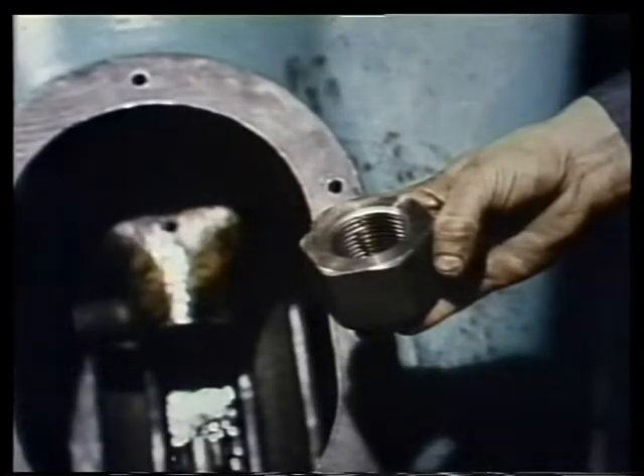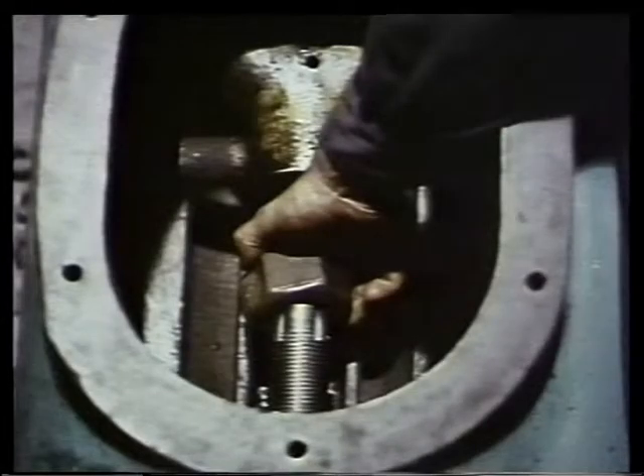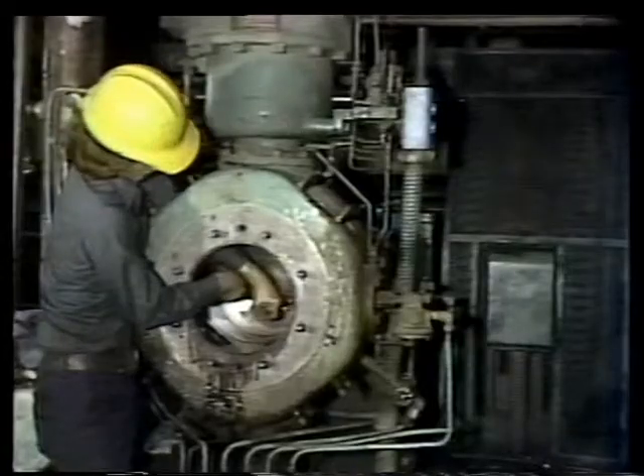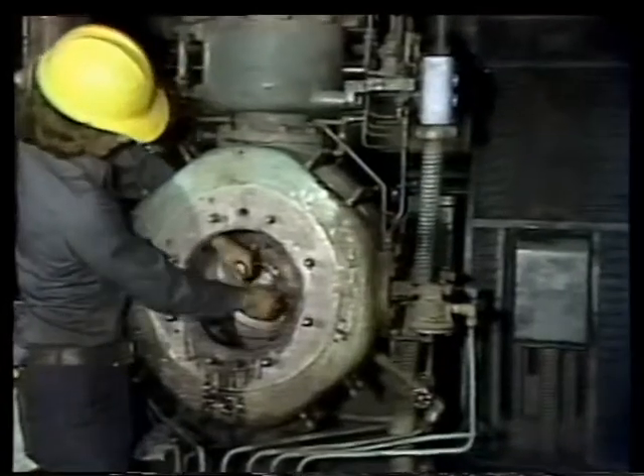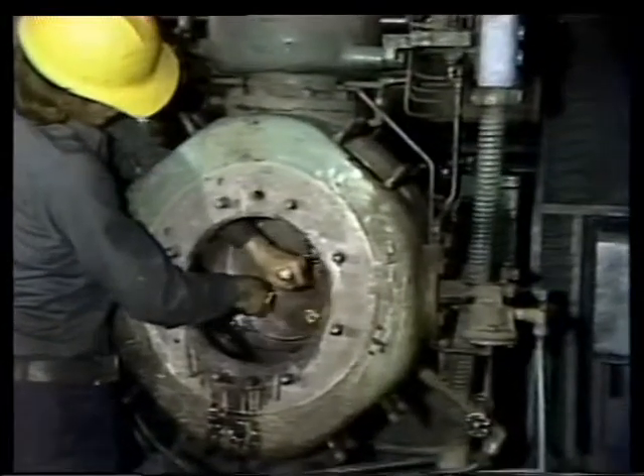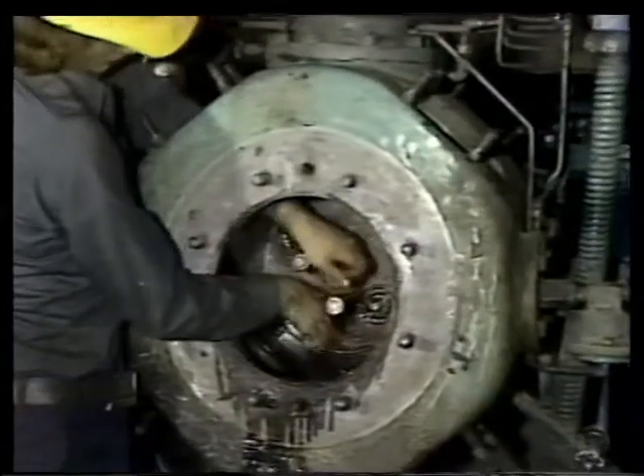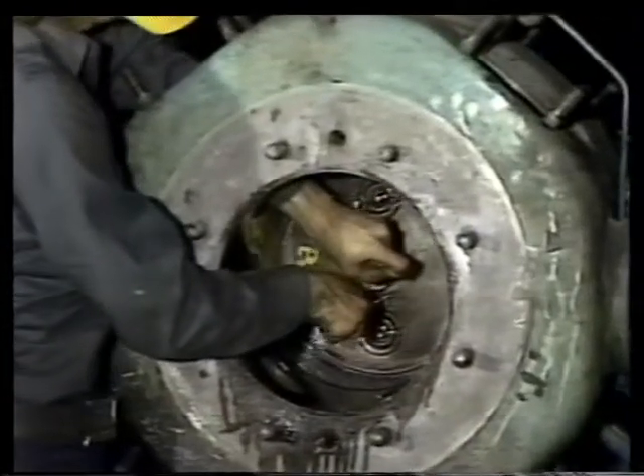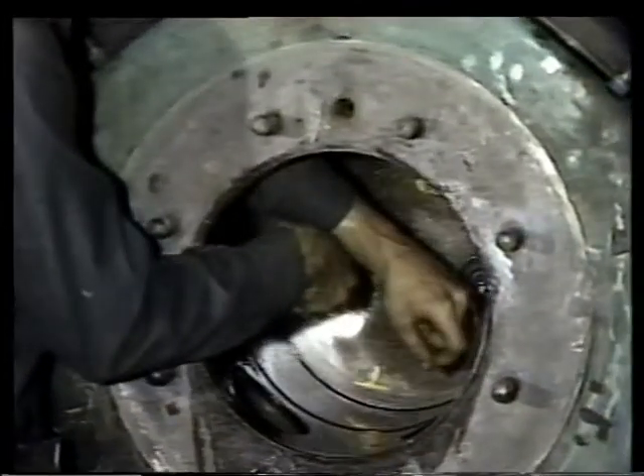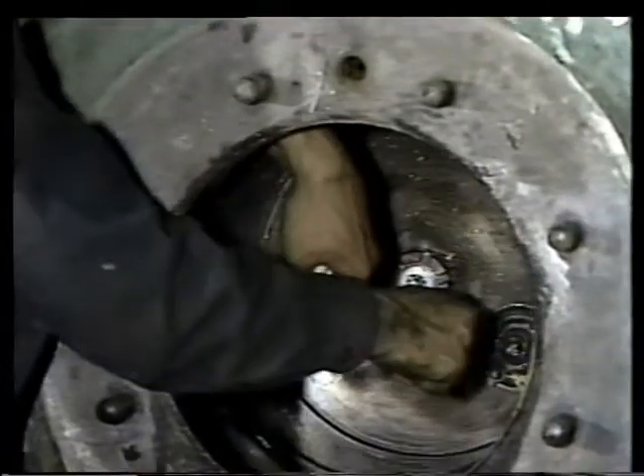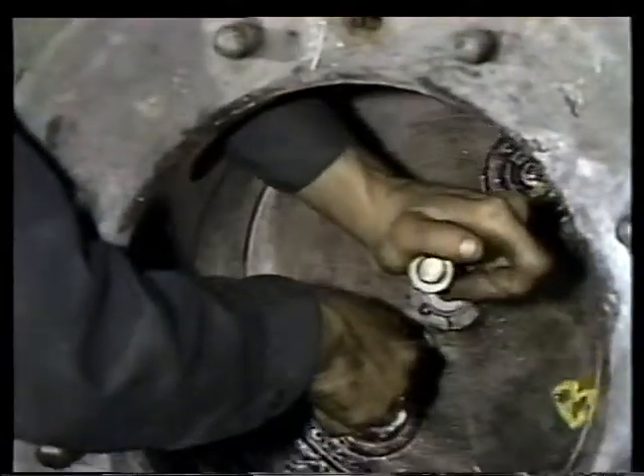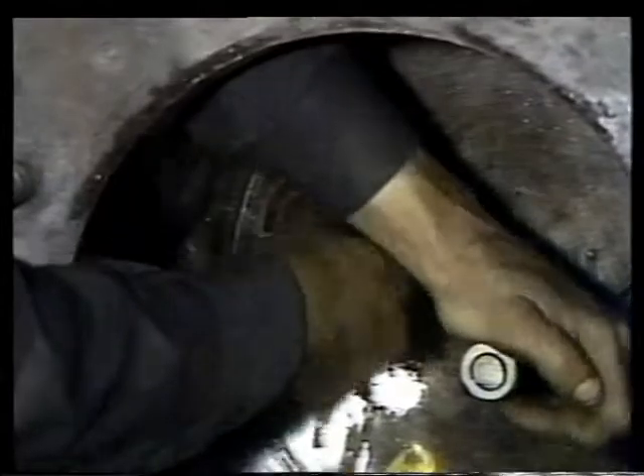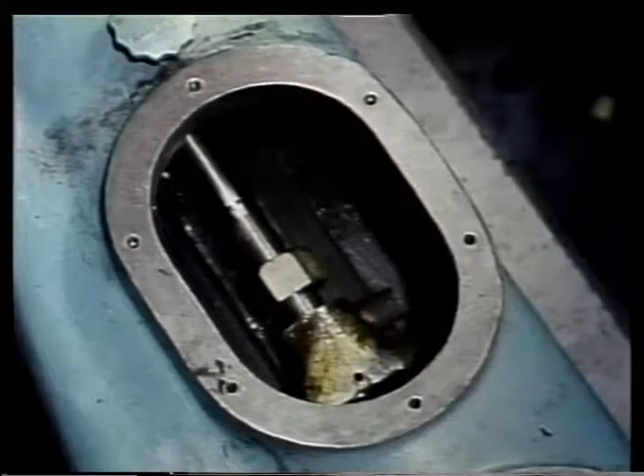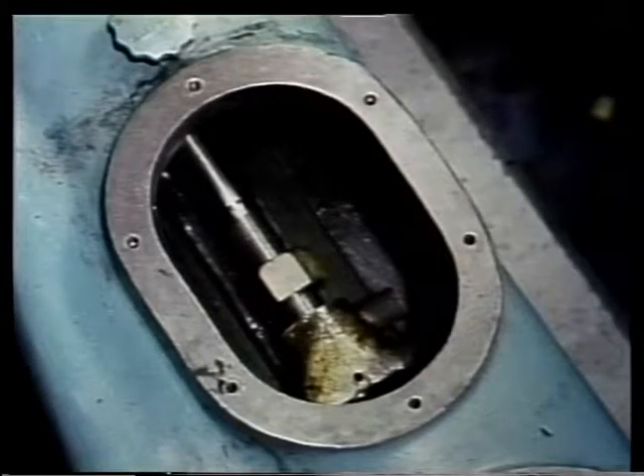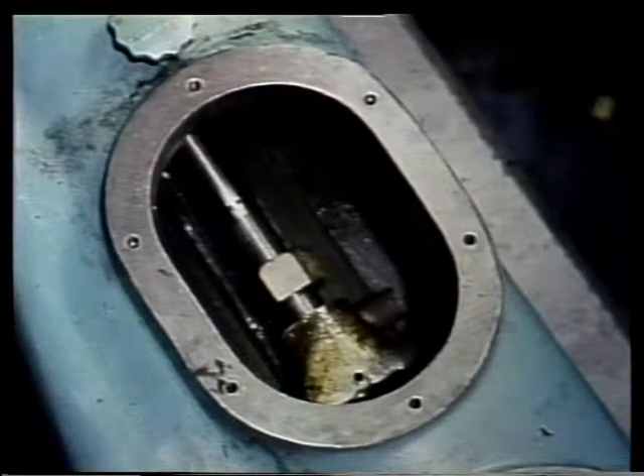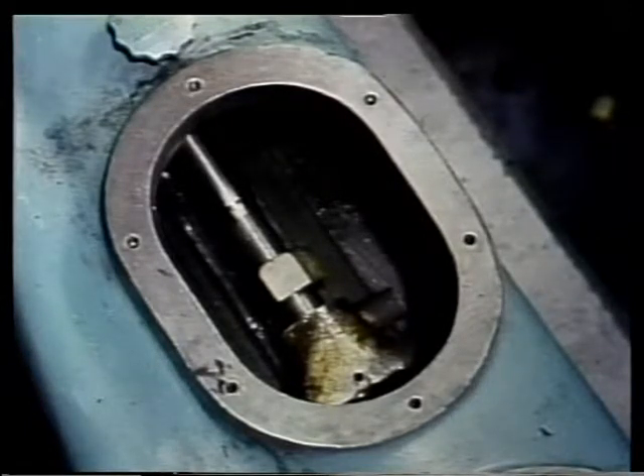The next step is to screw the piston rod lock nut onto the piston rod. Then you can screw the piston rod into the crosshead. With the piston rod in position against the crosshead, turn the piston by the two long bolts. Screw the piston rod into the crosshead until you have the piston in approximately the right place in the cylinder. You'll make a final adjustment later, but for now, a visual check of how far the piston rod is screwed into the crosshead will do.